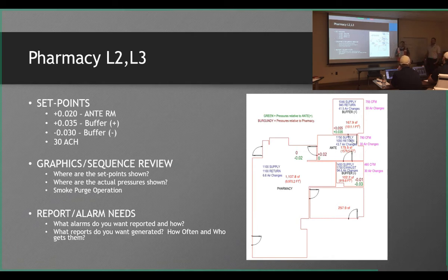Good job of making sure they sealed everything. Yeah, they did too good of a job. In the walls, there's not enough leakage. And so really, funny thing is that one room, 60 CFM, we would go from above and be able to set point out of bounds. Only 60 CFM. You know, trying to measure 60 CFM is crazy. Yeah. Right? So, it's worth thinking about, right?